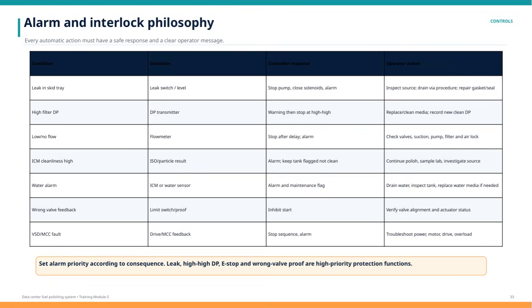Incorrect valve feedback is caught by limit switch or proof signals, which inhibit startup until valve alignment and actuator status are verified. Finally, faults in the variable speed drive or motor control center, detected through system feedback, cause the stop sequence and alarm, requiring troubleshooting of power supply, motor, drive, or overload issues.